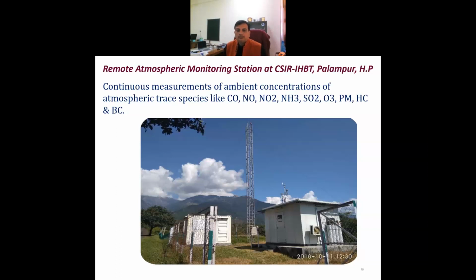In this regard, CSIR NPL has established a remote atmospheric monitoring station at CSIR IHBT Palampur, Himachal Pradesh. Here we have an air quality monitoring station in which we measure the concentration of ambient nitrogen oxide, nitrogen dioxide, ammonia, hydrocarbons, particulate matter, and black carbon, as well as meteorological parameters, since its inception for time series observation. We also measure weather data like rainfall, temperature, relative humidity, and wind direction.